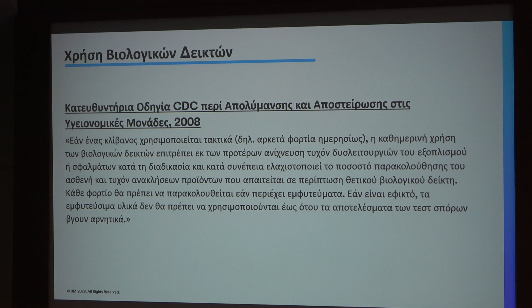One of the most commonly asked questions is how often we should use it. Standards don't tell you how often. They tell you what type of biological indicator will help you, but when you look at the guidelines, you can find more information. There may be different approaches. Again, the most important thing is your resources. You know your sterilization units better than everyone, and if you see that, for instance, the autoclaves are not so new, or the water system is not very well designed, it means that you will need more information about steam quality, and as these indicators provide lethality, these will be the best tools to use.